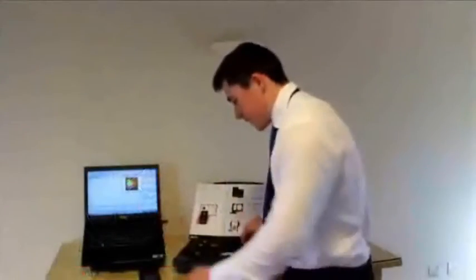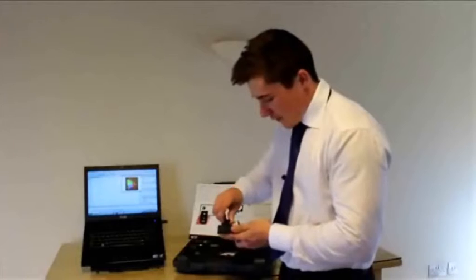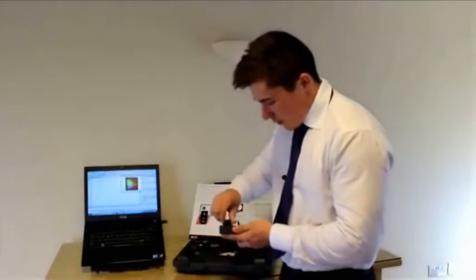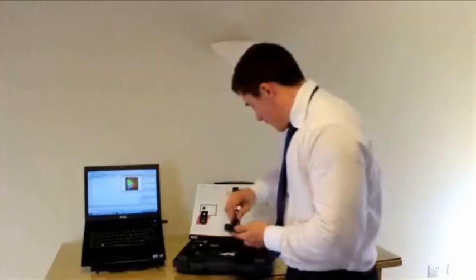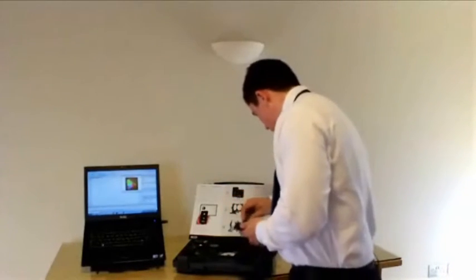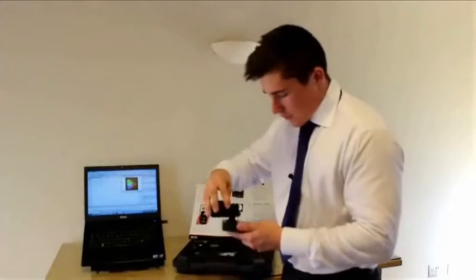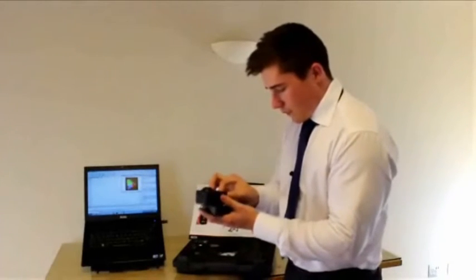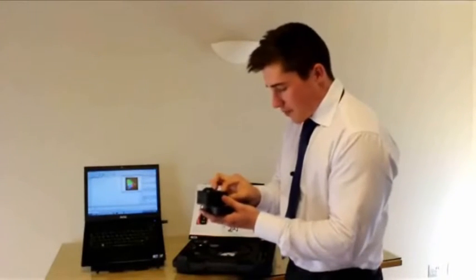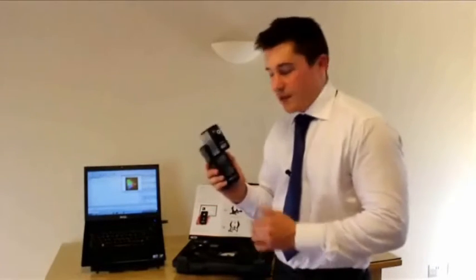The second accessory is the GL optic 48mm integrating sphere. The sphere simply screws on, as shown here, and the software will recognise that a different measuring accessory has been attached and apply the correct file for a lumen measurement rather than a lux measurement.